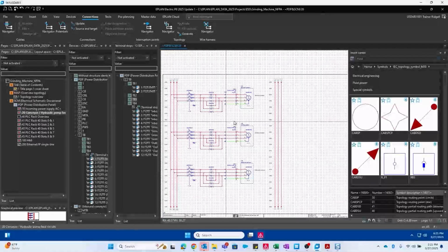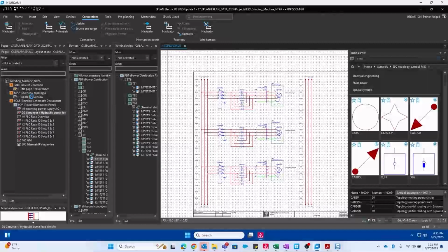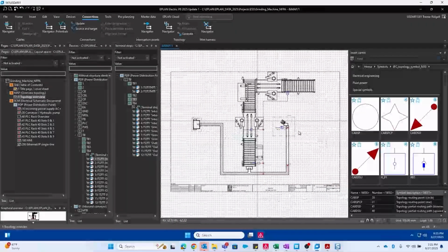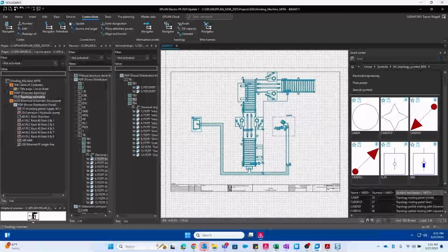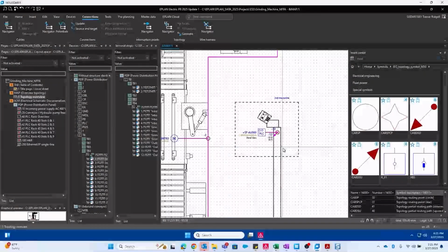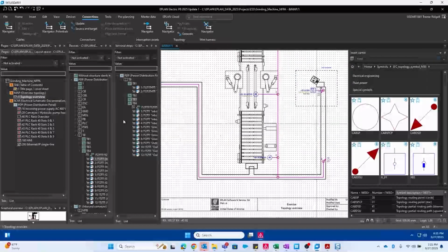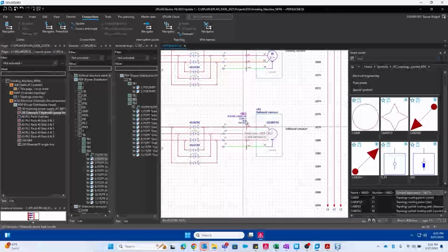So it also included our ground bus bar. That's okay. Shouldn't be a problem. Let's go back to the topology page and let's do our routing. So Control A to highlight everything on the page, connections, and then in the topology section we click route. And indeed, everything is purple, so we know everything did route. Okay, and then if we go back over here, you'll see you have your cable lengths and everything filled in, right?